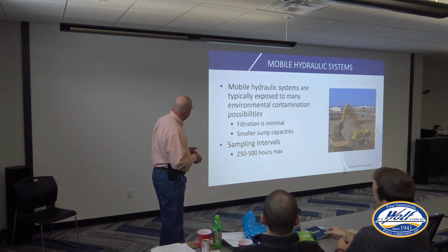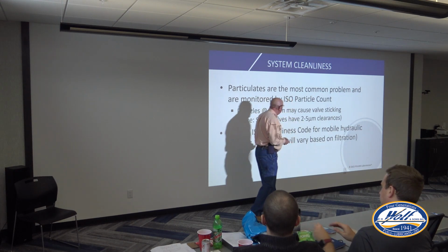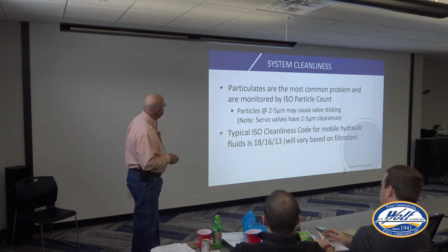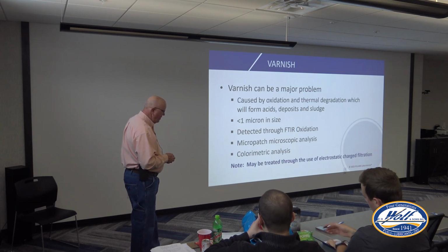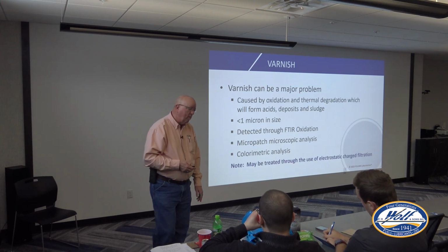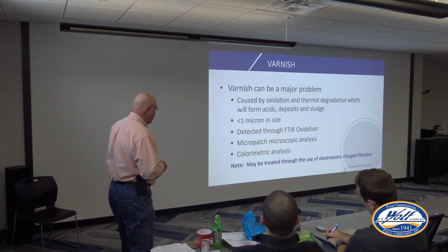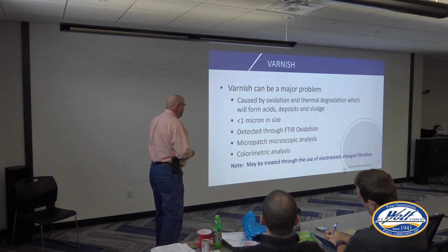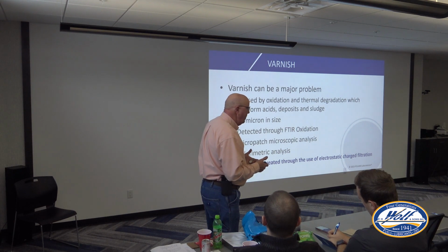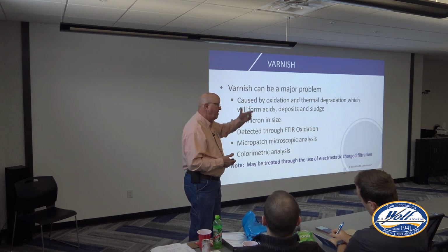So I thought that was pretty interesting that he would share that from the real world. Okay? And usually with these hydraulics, we're worried about this stuff we can't even see, 2 to 5 microns. It's going to get into those clearances and cause us all kinds of issues. Varnish, that's something the industry is starting to talk more and more about. We do have some testing that we run, called varnish potential. We're going to look at that to say, okay, what's the remaining life of this oil? When it gets down near the end of the life, that's when you can see varnish start to happen.